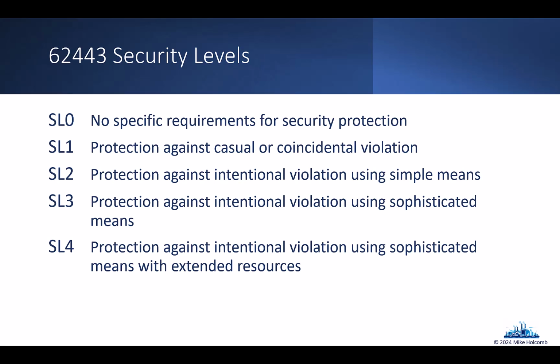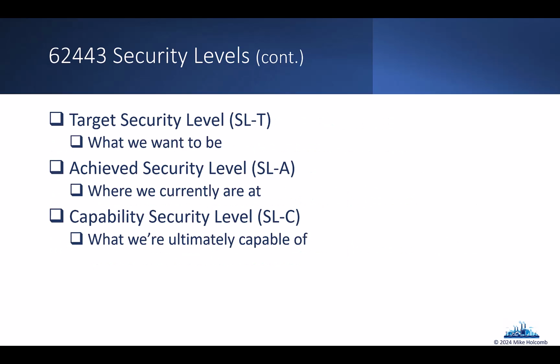But I want a little bit extra protection when it comes to those mission critical zones, like the SIS, or, think in manufacturing, the manufacturing execution system, the MES, that coordinates all of the manufacturing to actually occur. I want that additional protection there. So I'm going to assign a target security level of 3 to those mission critical zones.